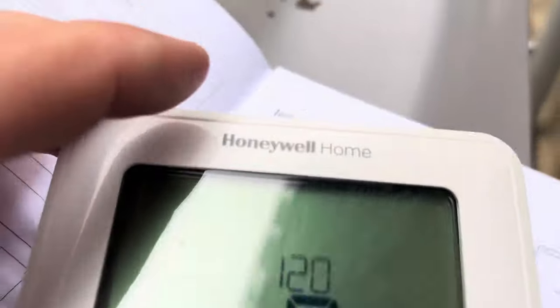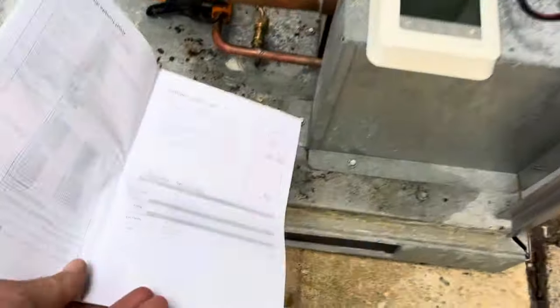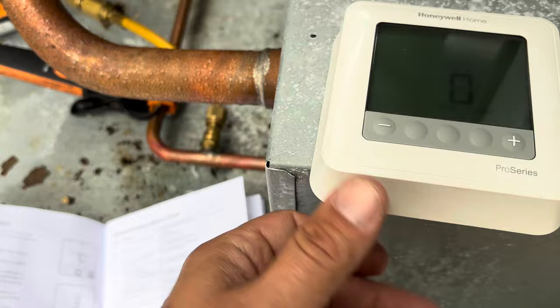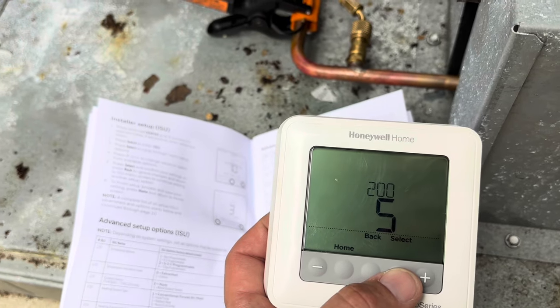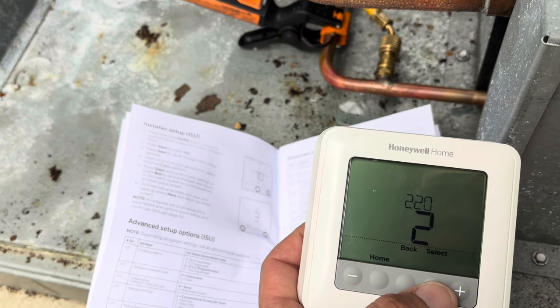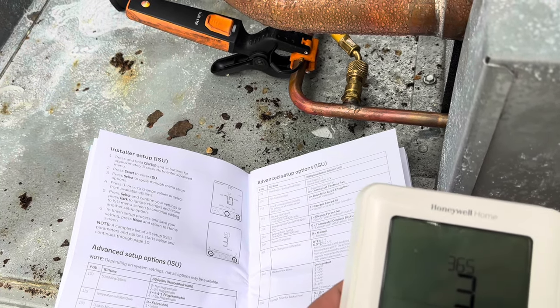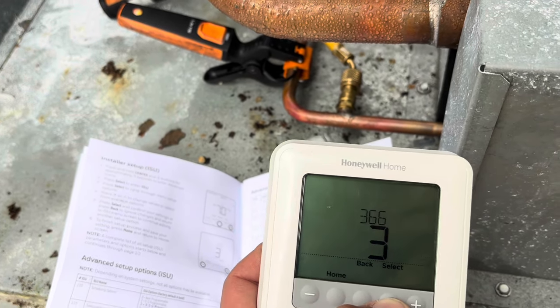We've got the thermostat here and we're going to go through its settings because this is a two-stage unit. Parameter 130 — we don't have an outdoor sensor. Parameter 200 — this is our cooling system, so we're set to cool only. Parameter 220 — we have two compressor stages. Parameter 365 — this is our cycles per hour; somebody had this set to six and we want that at three.